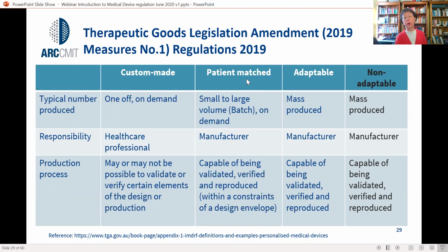What is patient-matched? Well, now it's not one-off. We're looking at batches. So it's a small batch. There's no specification of what small or large volume means. It's just batch, but batching means that, if they were audited, the responsibility of the manufacturer is that they must be able to show that that batch is using, for example, the same manufacturing method for that particular batch, the same lot of the raw material that's being used to produce the final device itself. And there's more onus on the manufacturer to be able to validate, verify, and reproduce the device.